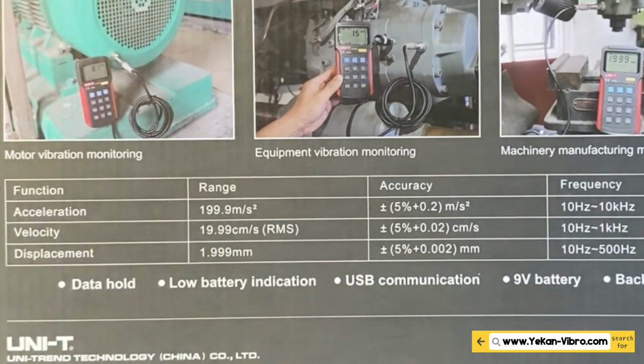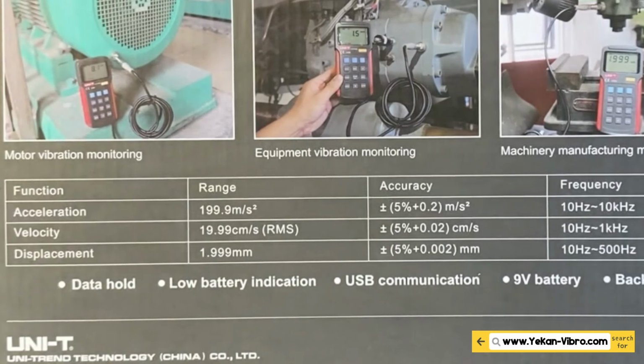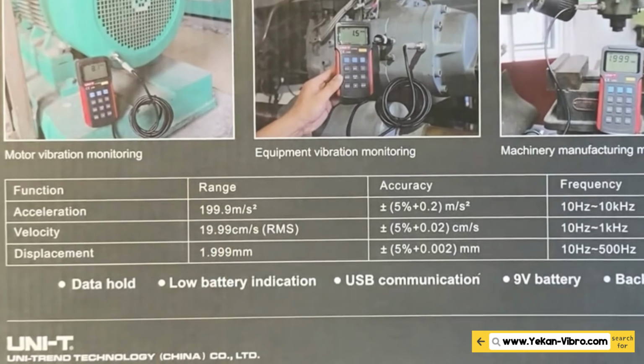What trouble? You go to a technician, or a manual or a datasheet says that if, for example, you measure vibration of this bearing and it was more than 2G, you should know that it needs maintenance and has a fault. Usually devices themselves come with this unit conversion, meter per second squared or G, done by software. That means in its settings you set that you want acceleration based on G. Unfortunately, it does not have it, or if someone says okay, I will convert it, well, it makes it difficult. And one worse problem: the datasheet says 2G RMS, here you are reading peak, and there is almost a 20 to 30% difference.